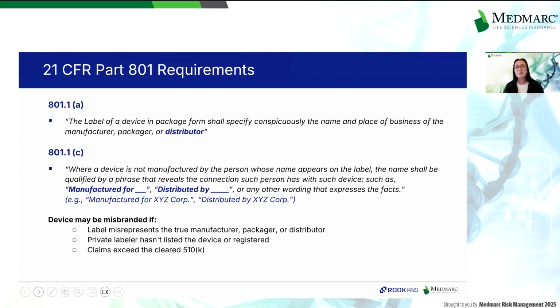A device may be considered misbranded if the label misrepresents who the manufacturer is, the private labeler hasn't registered or listed the device as required, or if the label includes claims that go beyond what is cleared in the original 510(k). So clear, truthful, and properly qualified labeling is not just best practice, it's a regulatory requirement to stay compliant and avoid enforcement actions.